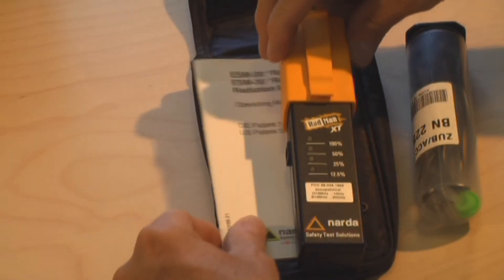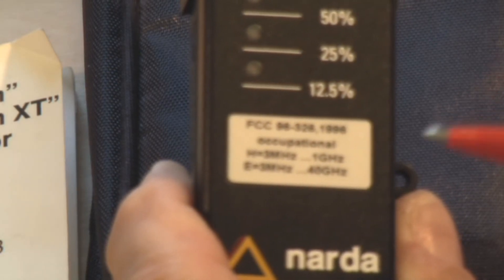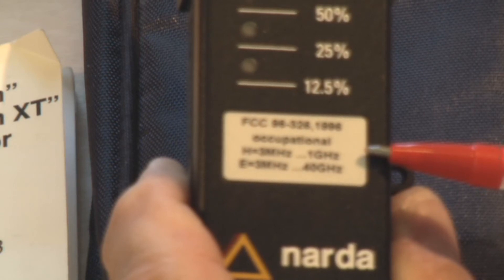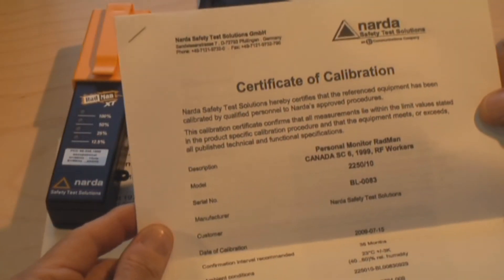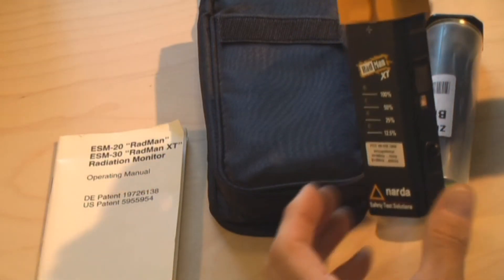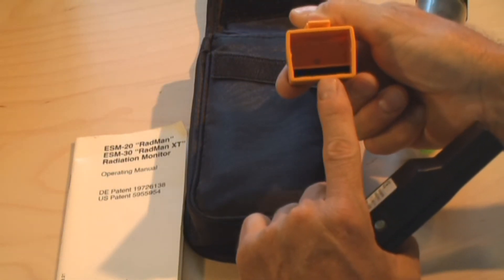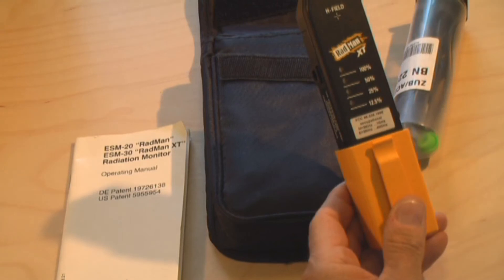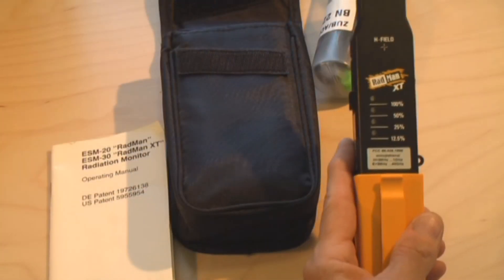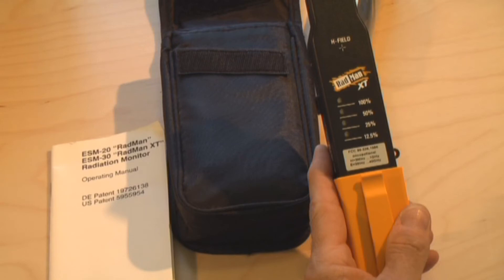This is the Radman XT. The user's manual is straightforward and easy to use. This monitor is the only one that claims to detect both the E electric field and the H magnetic field. The E field is detected between 3 MHz and 40 GHz, and the H field between 3 MHz and 1 GHz. A certificate of calibration is supplied to traceable standards. As a personal monitor to be worn in a pocket, the yellow cap stays on to reduce interaction with the body. The second mode is using this monitor as a peak detector — you must remove the yellow cap with absorber material and typically place it on the bottom, giving a fairly isotropic detector for quasi-survey use. The unit is powered by two standard AAA batteries and also has a fiber optic output for remote data collection.